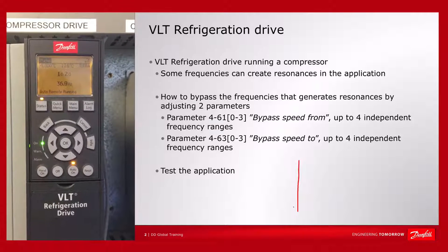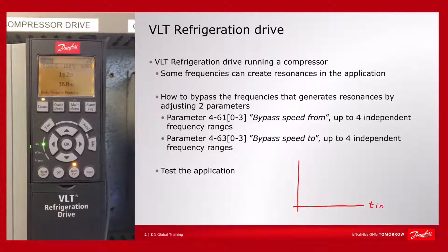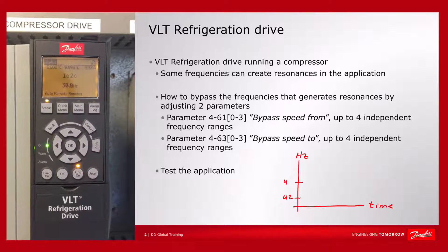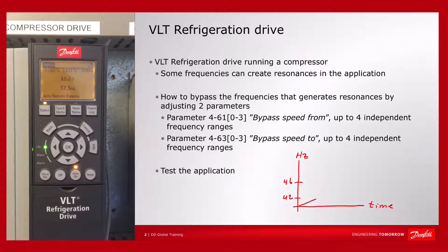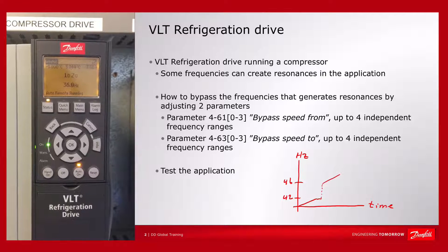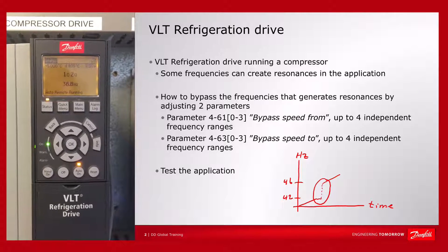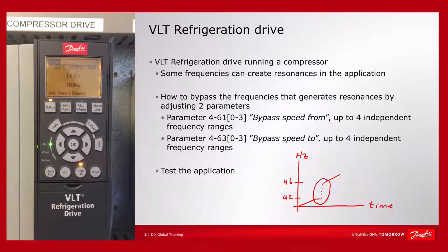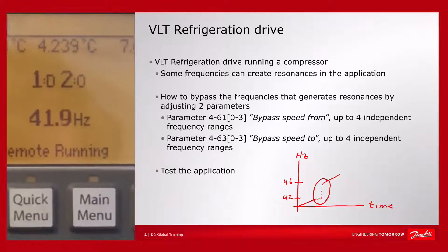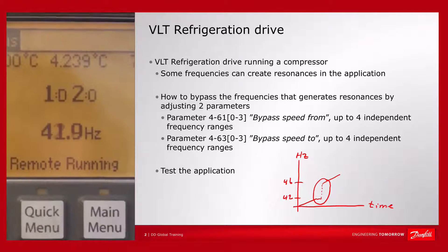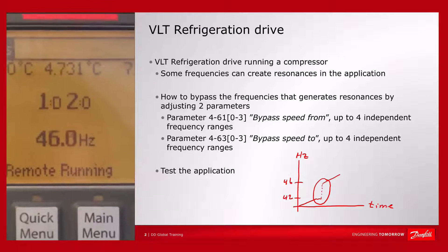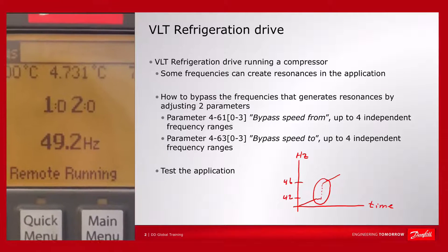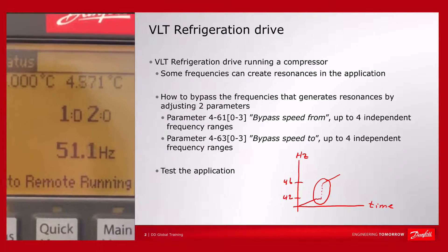The drive ramps up and should reach 42 Hz where it stays for a while. The drive reaches 42 Hz, stays there, and then quickly skips to 46 Hz, eliminating the resonances in the system and still trying to reach the desired temperature.